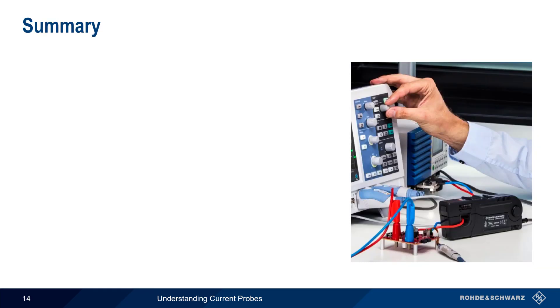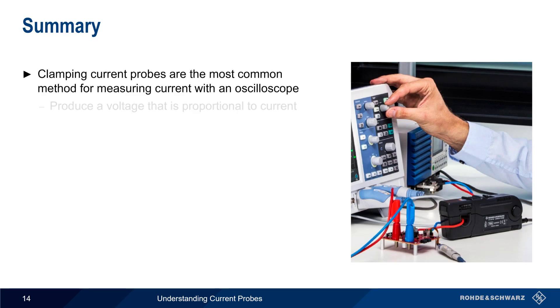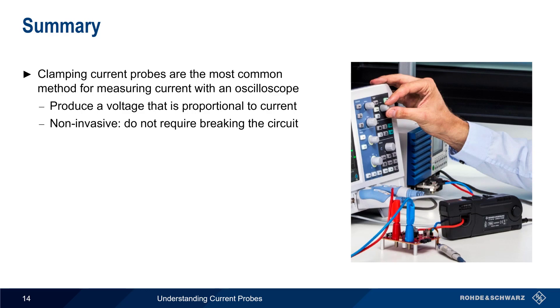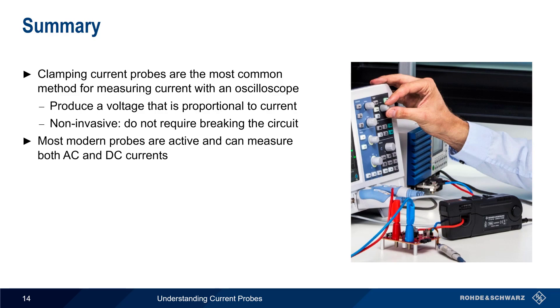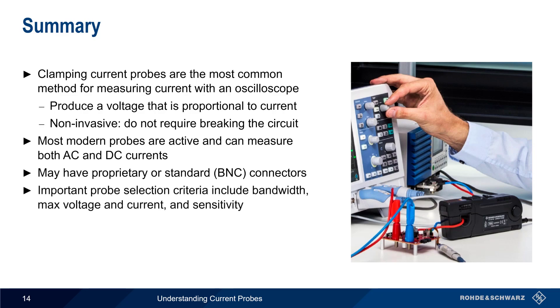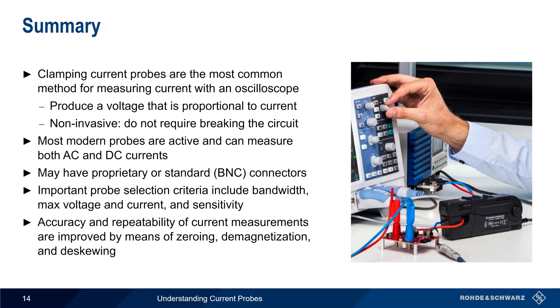Let's end with a brief summary. Clamp-style current probes are the most common method for measuring current with oscilloscopes. These probes produce a voltage proportional to the measured current and are non-invasive — they don't require the circuit to be broken. Most modern current probes are active and can measure both AC and DC currents using a combination of a current transformer and a Hall effect sensor. Probes may have proprietary or standard BNC connectors, each with advantages and disadvantages. Important parameters when choosing a probe include bandwidth, maximum voltage and current rating, and sensitivity. Measurement accuracy and repeatability can be improved by zeroing, demagnetization, and deskewing. This concludes our presentation, Understanding Current Probes. For more on current measurements, probing, or other oscilloscope-related topics, please see the links in the video description.